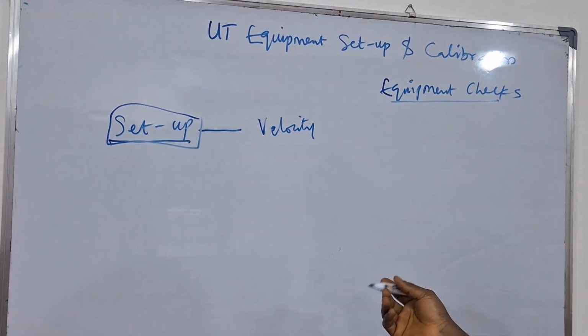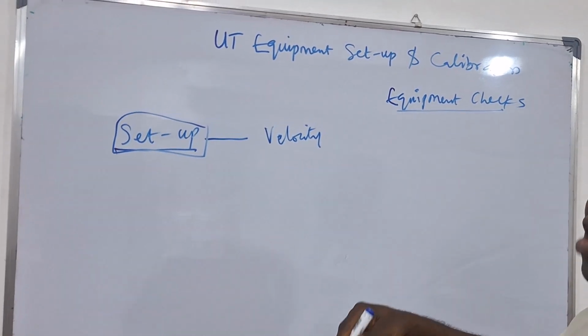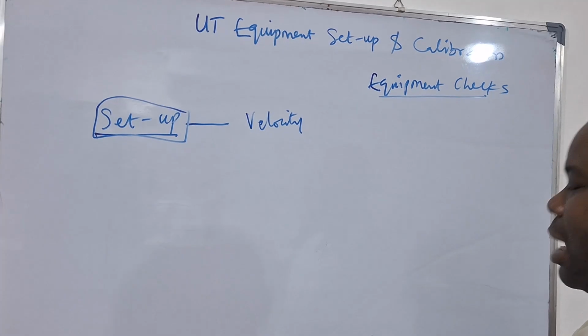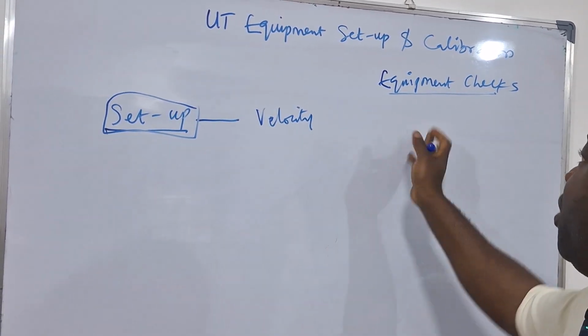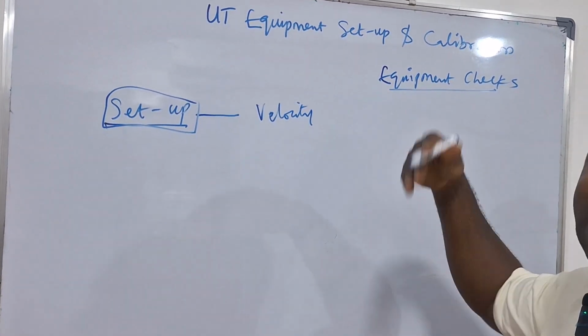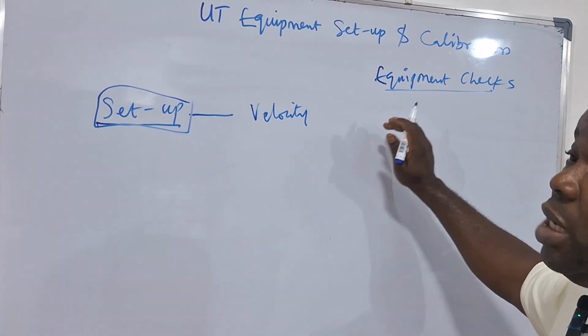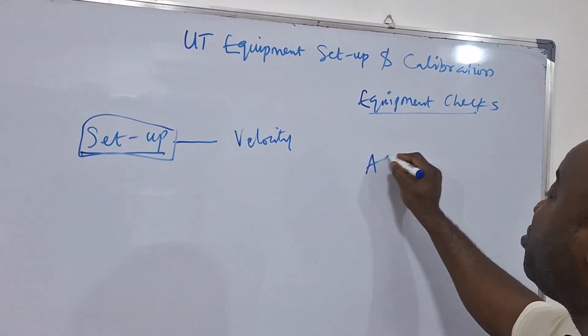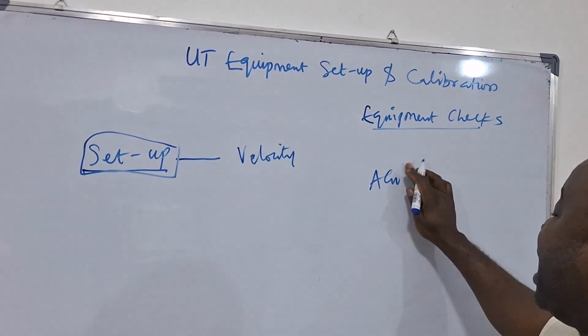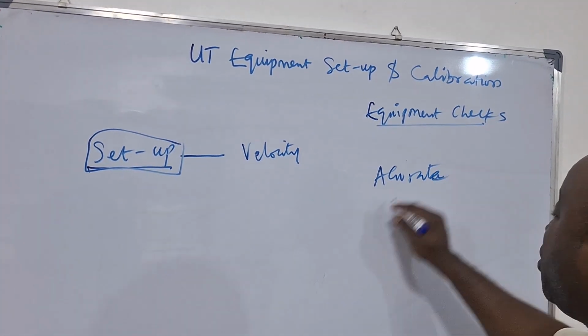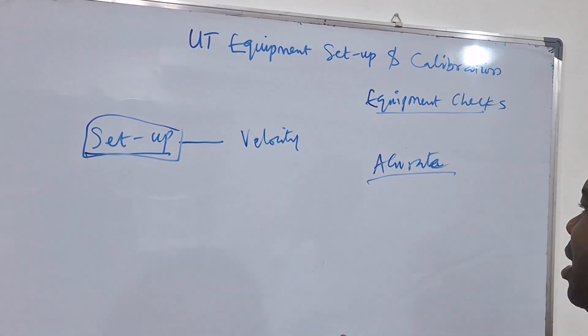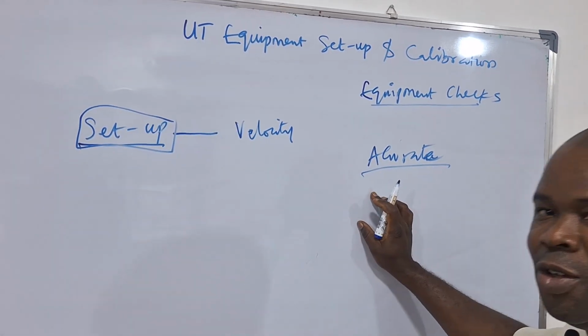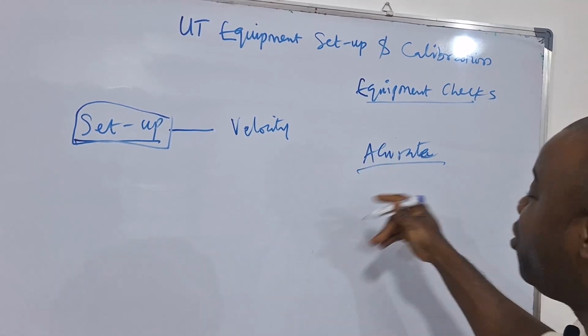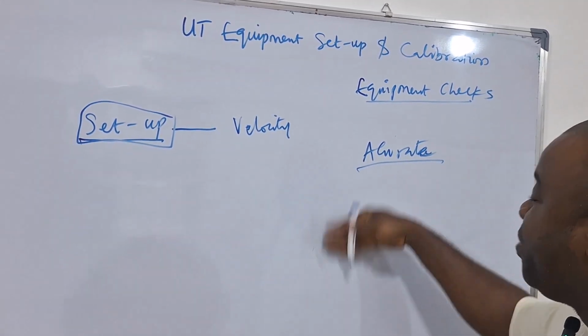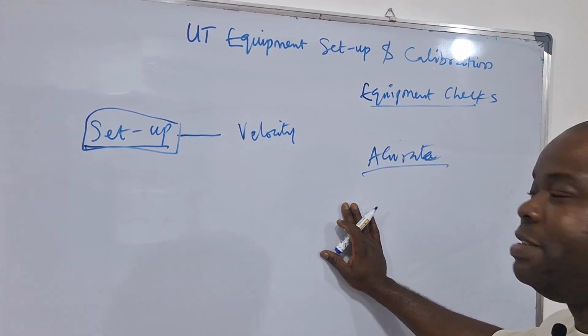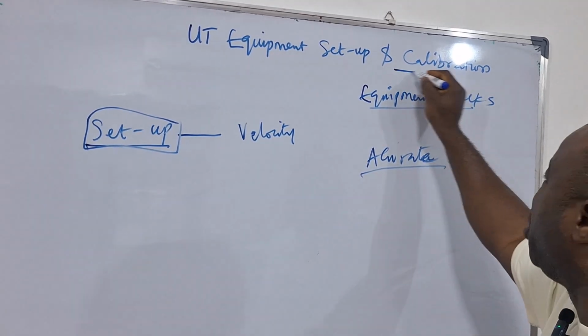A very popular question that some people will ask is, if you do your setup and you try to maybe perform thickness or perform a wet scan, are you going to get indication? Yes, you are going to get indication. The only thing is that your indications will not be accurate in terms of their dimension. In the sense that if you are measuring thickness of a plate, if you do not calibrate, you will not get accurate thickness. But you will still be getting your back wall echoes. They will not be where they are supposed to be on your UT machine. So that is where calibration comes in.